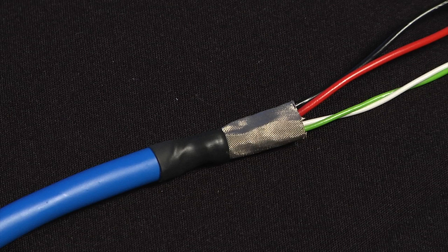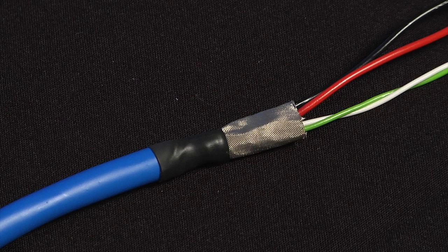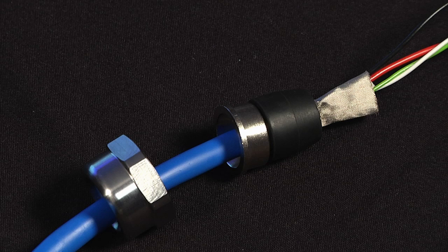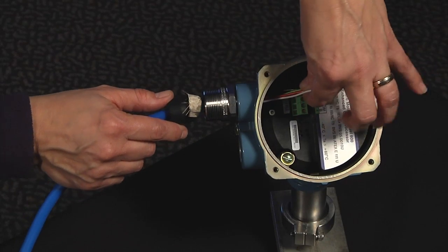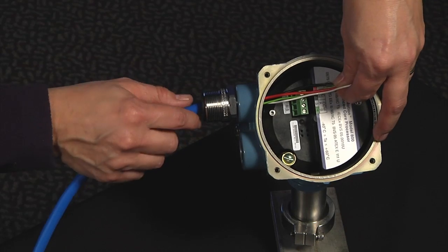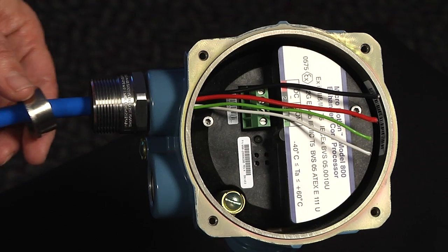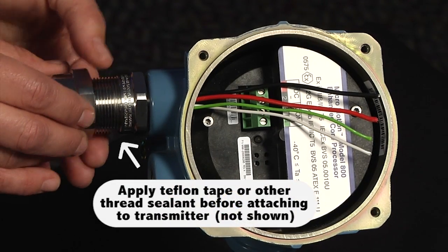Now you are ready to put the gland together and attach it to the device. To do this, slide the gland insert piece or pieces up to the beginning of the shield and then fold the shield back over the insert. Feed the wires through the conduit opening and push the insert all the way into the gland body. Bring up the gland nut and screw it down tightly.